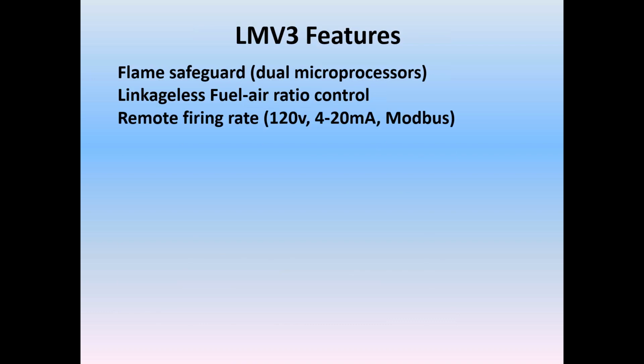It takes a remote firing rate. In other words, you have to send this thing 120 volts to increase the fire rate, decrease the fire rate, or a 4 to 20 milliamp signal from some external load controller, or you can control the firing rate through Modbus. What the LMV3 does not have is an onboard load controller like the LMV5. In that case, you have to get an LMV5 with an internal load controller. But many units today are using external load controllers because they simply turn it over to lead lag systems, master panels, BMSs, and let the LMVs do the flame safety and ratio controls. This is a common development as controls go today.